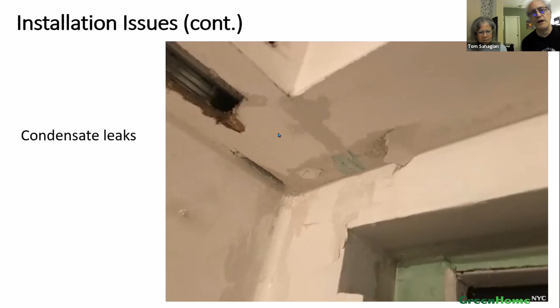We think it was probably a sheetrock screw from putting in the soffit, and it nicked the hose in such a way that the condensate, which was under pressure from the pump, leaked out and wreaked havoc. That got repaired and it's fine now, but it induces an additional cost for somebody, either the contractor or the soffit person. It's another reason you might choose not to send the condensate outside, because then those problems don't appear.